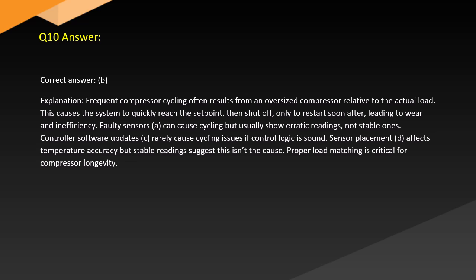Answer. Correct answer: B. Explanation. Frequent compressor cycling often results from an oversized compressor relative to the actual load. This causes the system to quickly reach the set point, then shut off only to restart soon after, leading to wear and inefficiency. Faulty sensors, A, can cause cycling but usually show erratic readings, not stable ones. Controller software updates, C, rarely cause cycling issues if control logic is sound. Sensor placement, D, affects temperature accuracy, but stable readings suggest this isn't the cause. Proper load matching is critical for compressor longevity.